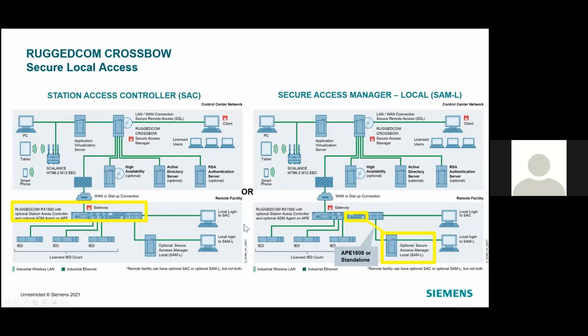Because this is in my substation and my connection to these devices goes through Crossbow, it's still doing the same keystroke logging and activity logging it would do for the centralized server, just locally. So when the WAN interface is reestablished, I can see that someone logged on to local access and what they did to these downstream devices, all centrally consolidated for triaging, event calls, or root cause analysis later.